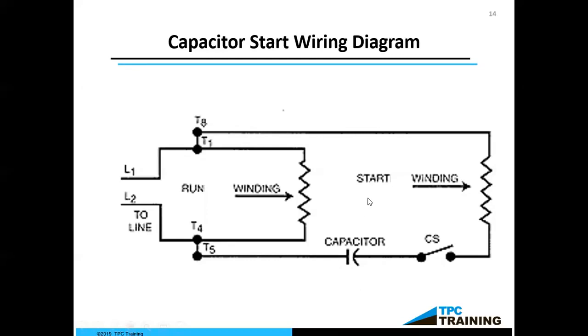But once we build up to 75% of the RPM of this motor, this centrifugal switch will open up and take the start winding out, and we'd be just running on the run winding. So a lot of single-phase motors will have that capacitor start on them. So what can we do?